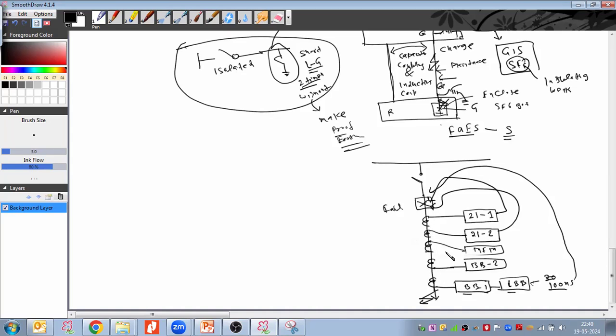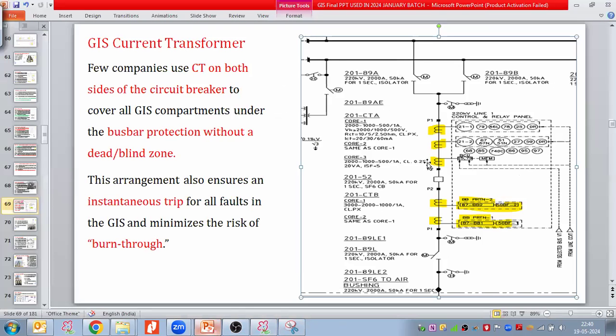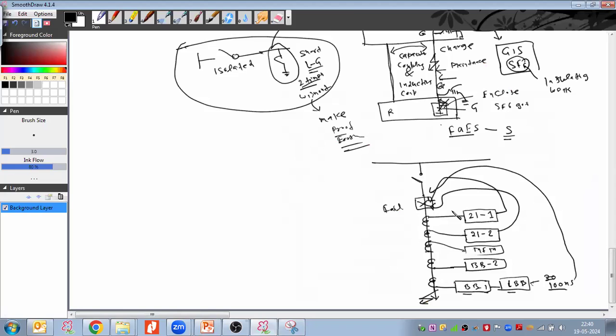Now what will happen? Fault happened, arc generated, fault current flowing. What you want is the tripping of the breaker as soon as possible, but there is a delay of 100 milliseconds, in case the breaker could not trip. So in this kind of arrangement, taking the distance here, taking the bus bar here, there would be one blind zone also created.